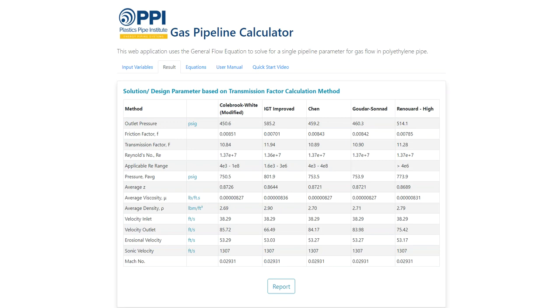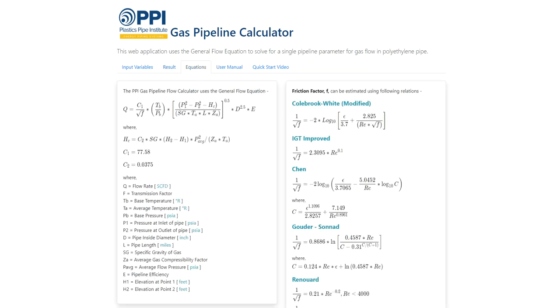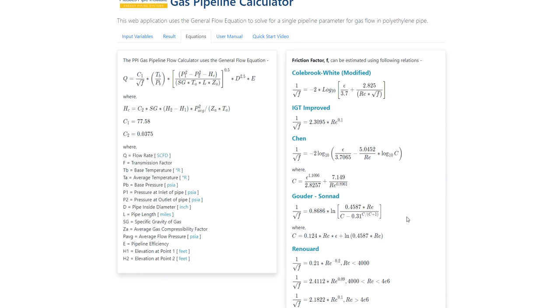The general flow equation and the five different methods of estimating frictional resistance used in the calculator are shown on the equations tab. F is the friction factor. The differences in the flow equations come from the assumptions used to reduce the general flow equation and to estimate the Darcy friction factor. The iterative process using the Colebrook-White equation typically gives the best results for estimating the transmission factor, taking into account the relative roughness of the pipe and the Reynolds number.